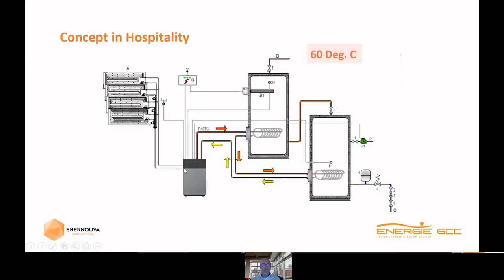So the refrigerant fluid will go in liquid mode into the panels, and it enters the panels at around minus 50 degrees. Then it will evaporate on the panel using the sun radiance and the heat, coming out as vapor. Then it's pulled by a compressor that compresses the gas up to 28 bars, raising the temperature to 72 degrees. Then it goes to the heat exchanger. This is the main heat exchanger located on the supply tank, and we do the heat transfer to the water.